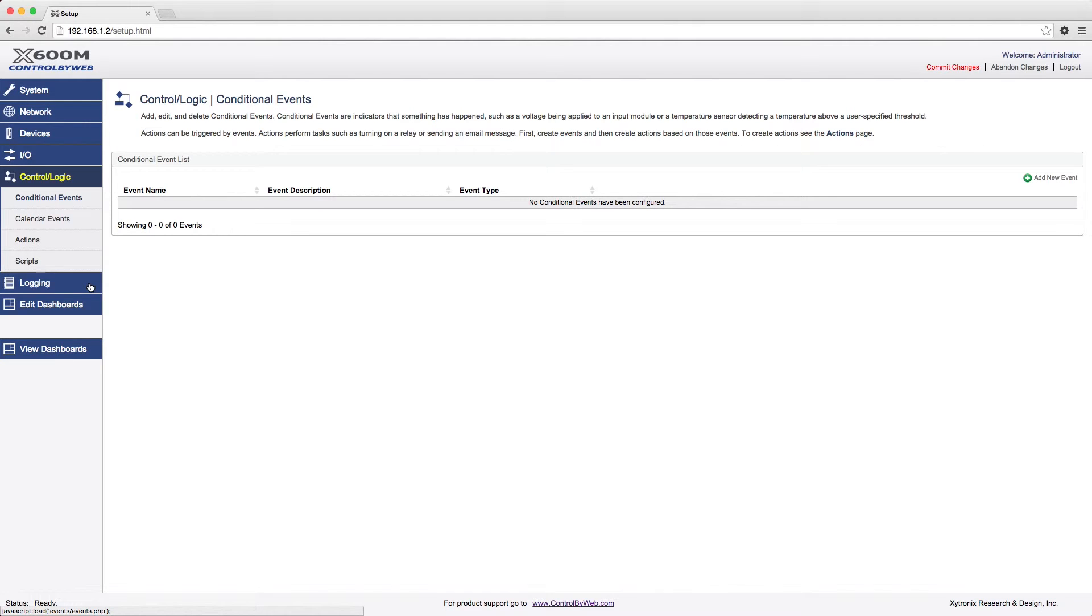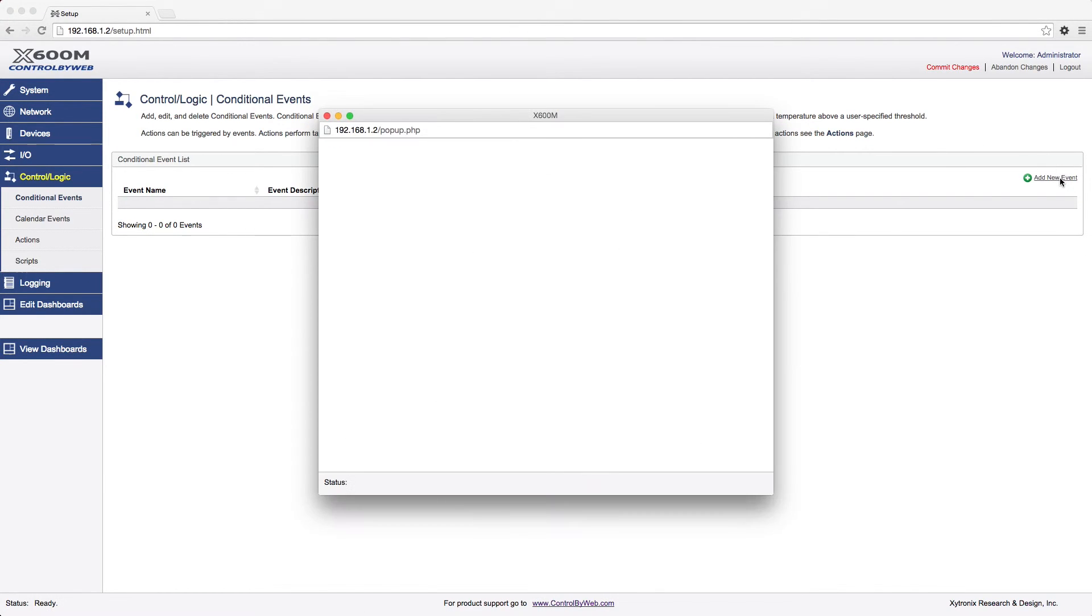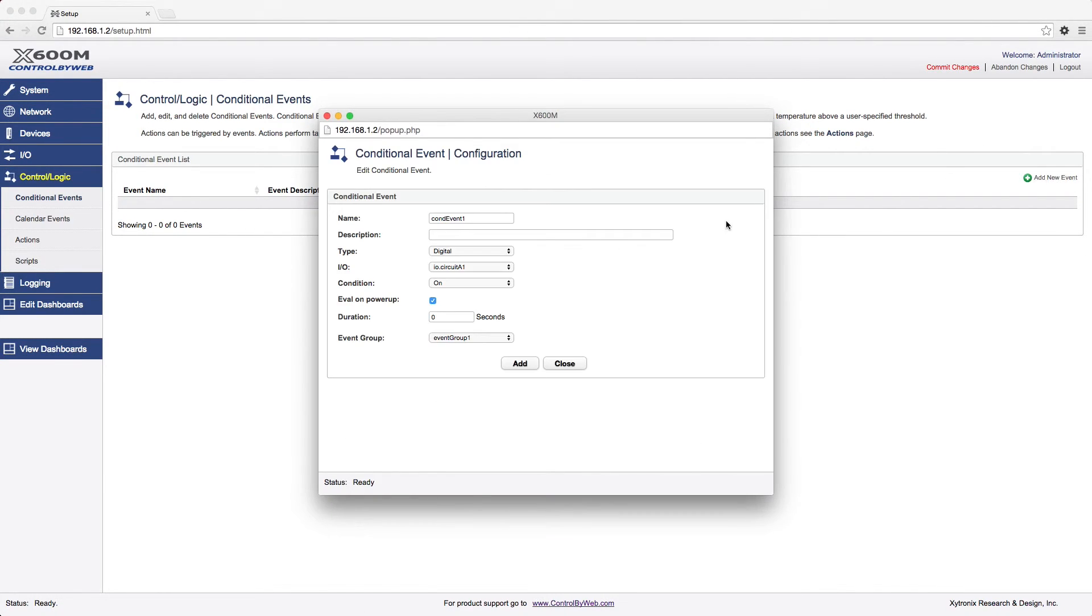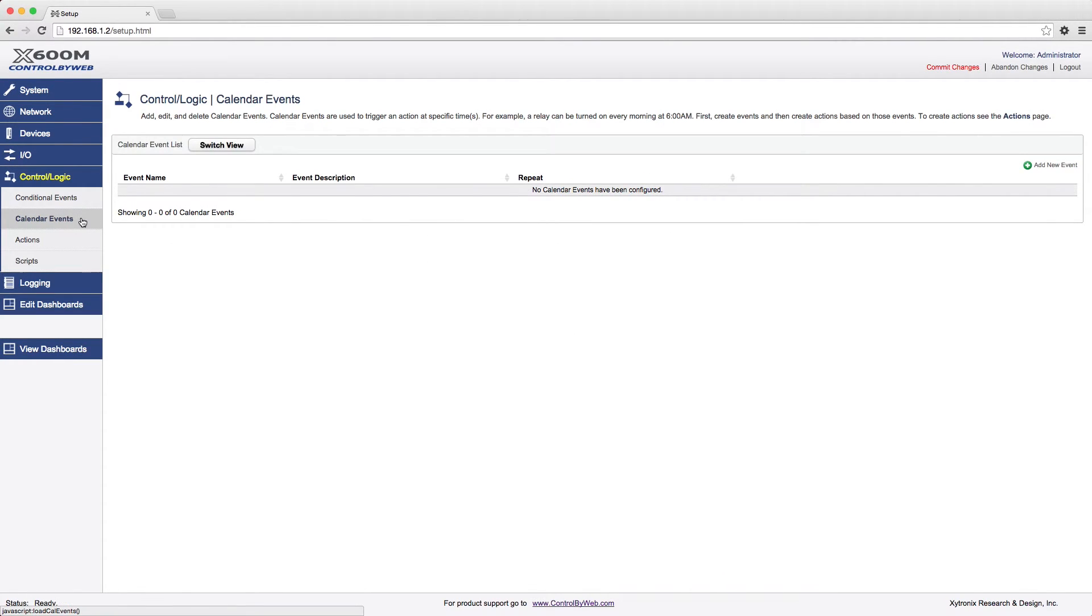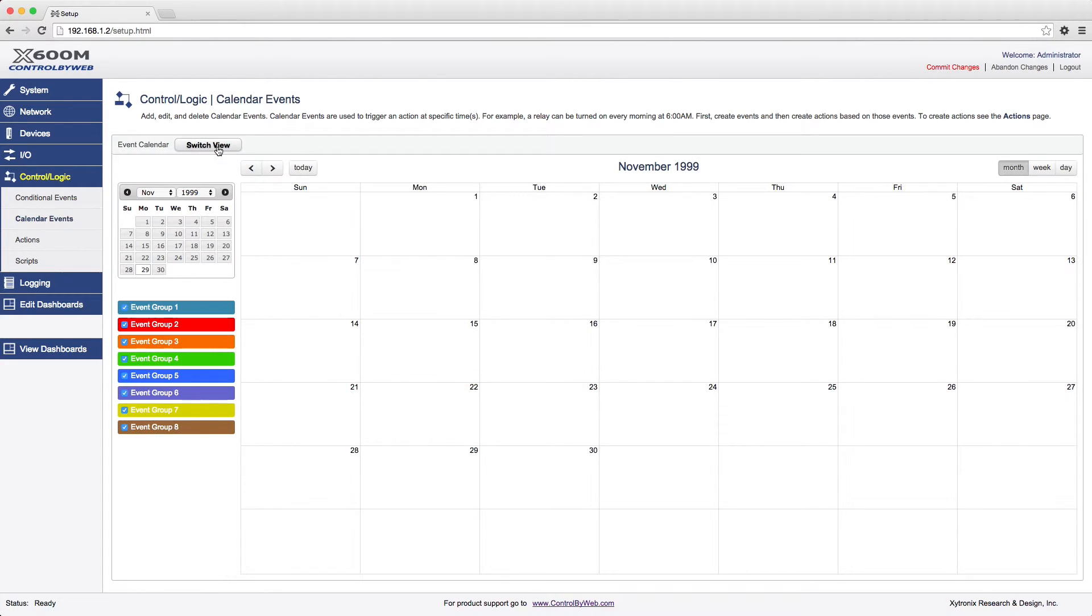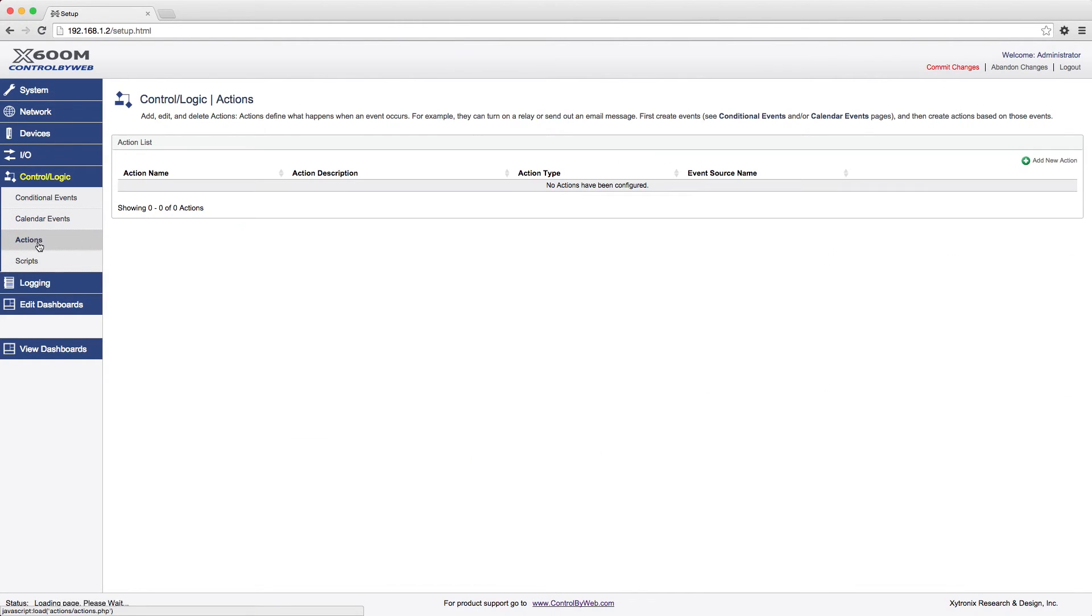Conditional events occur when certain criteria are met, such as temperature reaching a certain value. The conditions which generate an event can be either simple or complex. Calendar events occur at a specific time. You can specify one-time events or periodic events which happen repeatedly. Actions can include sending an email, turning a relay on or off, or initiating a data log. An event can trigger more than one action.